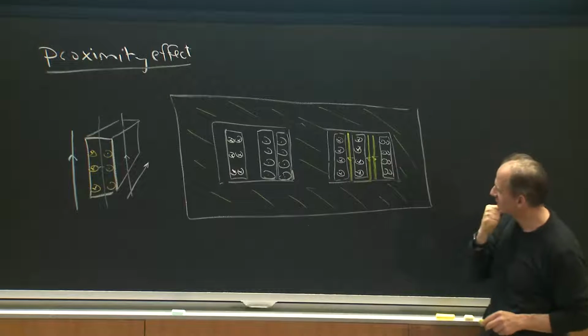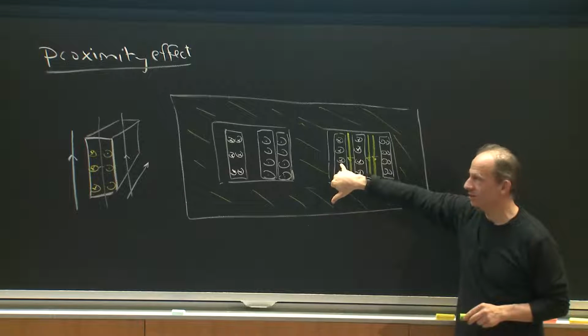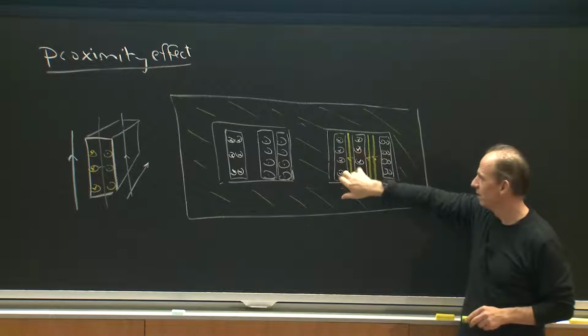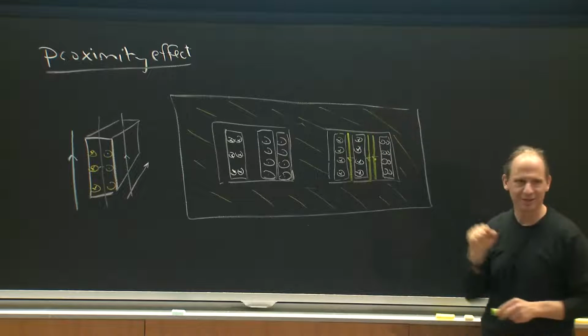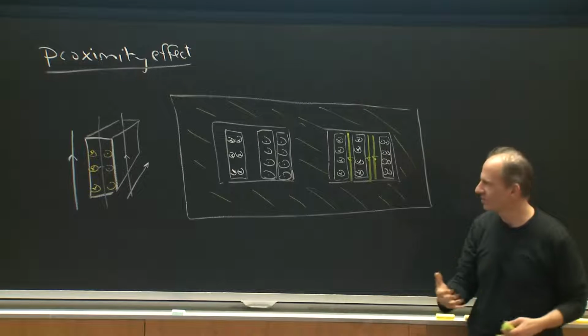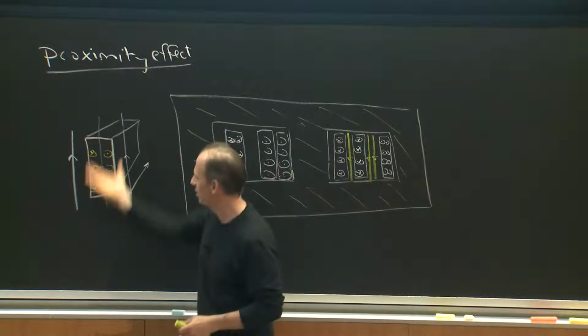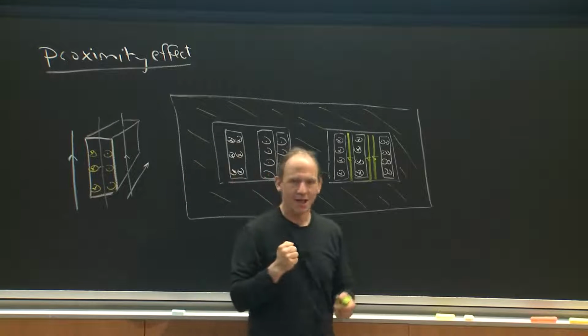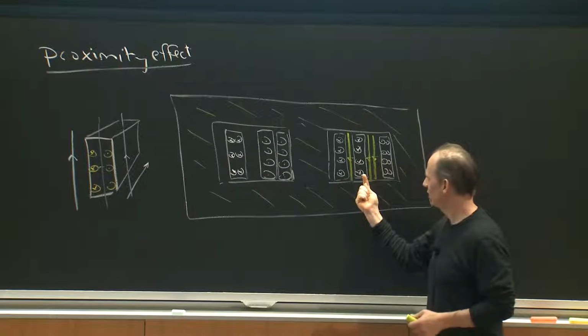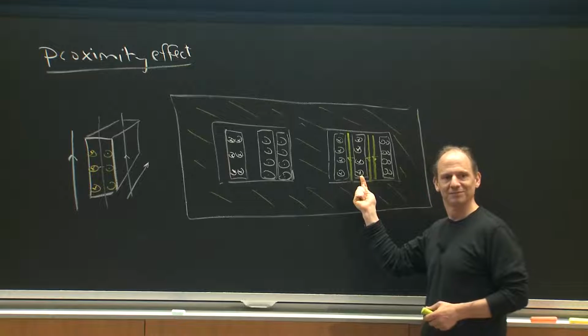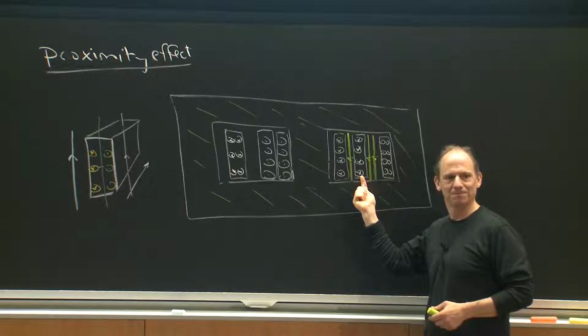So this is an example where fields owing to this layer are hitting this layer. Fields owing from these 2 layers would hit the next layer. And what happens is then I'm imposing fields on my conductor, and I'm going to get eddy currents in this second layer that's going to cause loss.